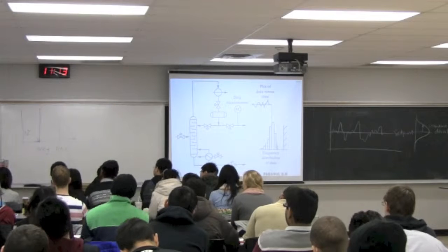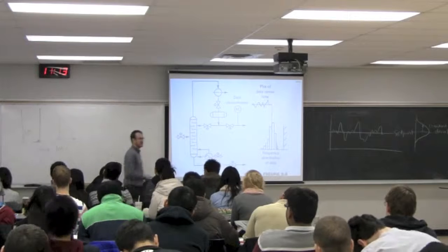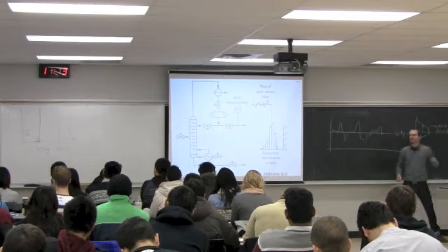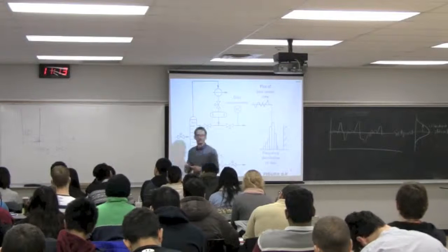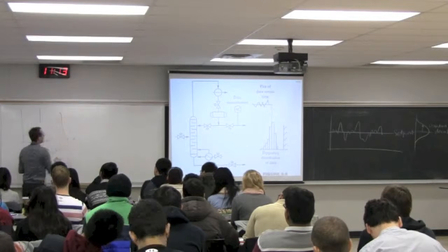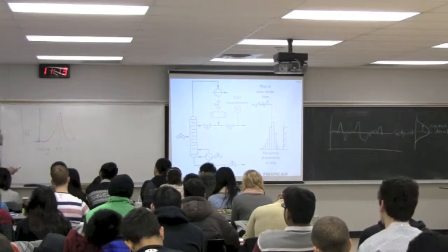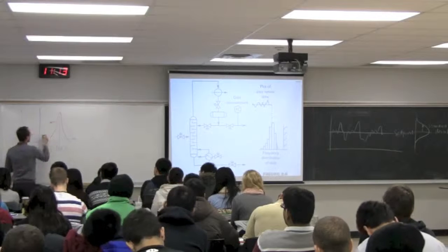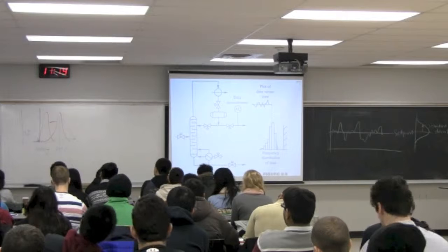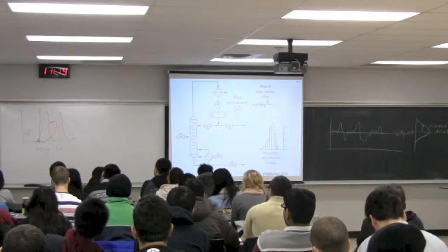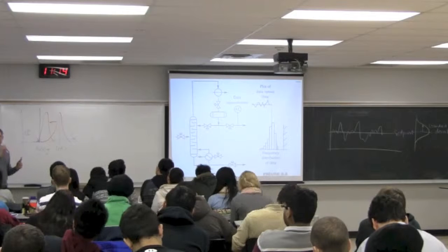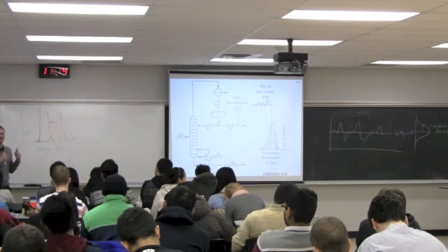So if you've got a way to reduce standard deviation, what can you do? Right, reduce overfill. So if you can make that standard deviation look like that, you can shift that histogram over and put it over here. So the moment you can reduce standard deviation, you can shift closer to your constraint. And that's how you quantify the benefit of the control system, is that savings.